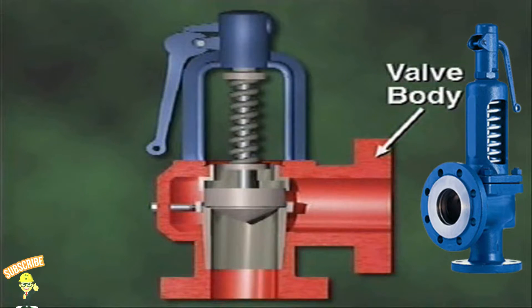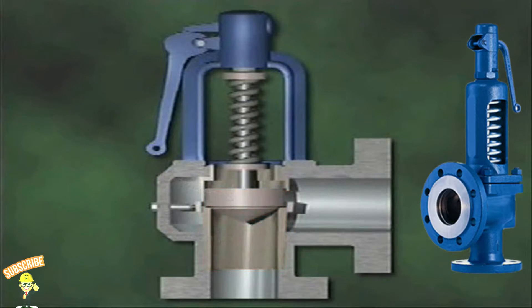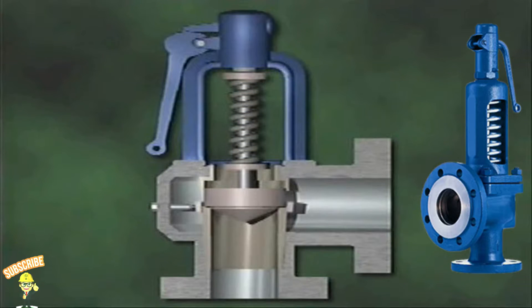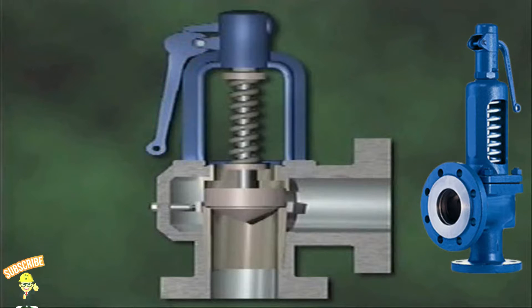The valve body directs the flow of pressurized fluid. The disc and seat seal the system closed under normal pressure. The disc is mounted on a stem. A spring holds the disc in place and the valve stem transfers tension from the spring to the disc. The release lever is used to trigger the valve manually while the system is operating to make sure that the valve works properly.